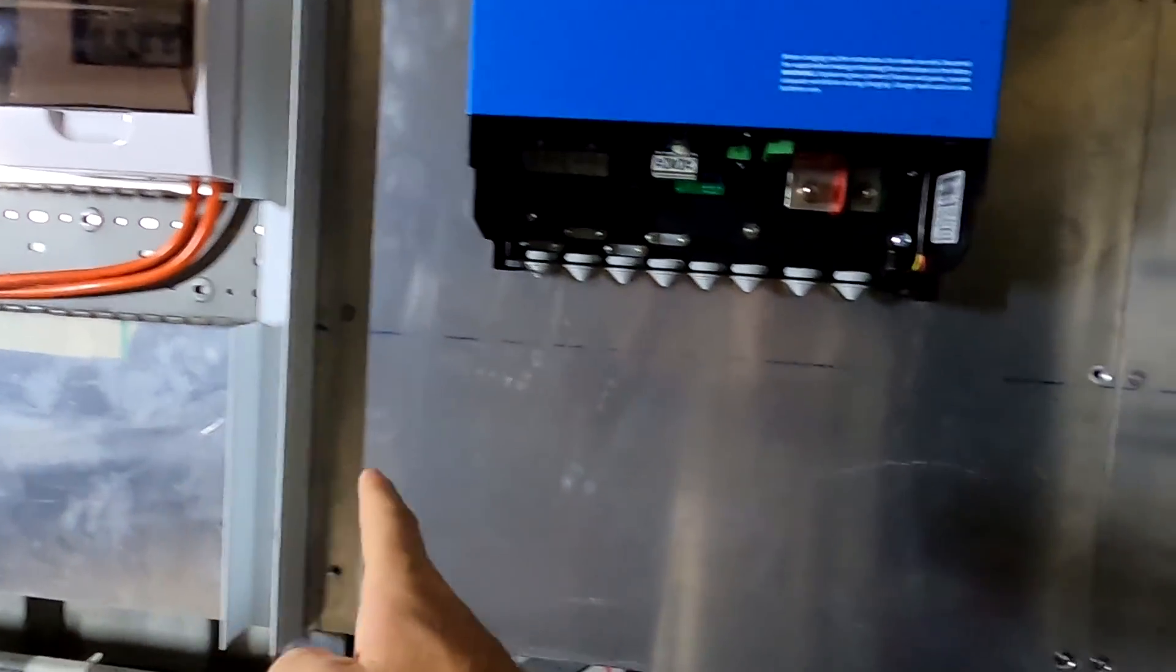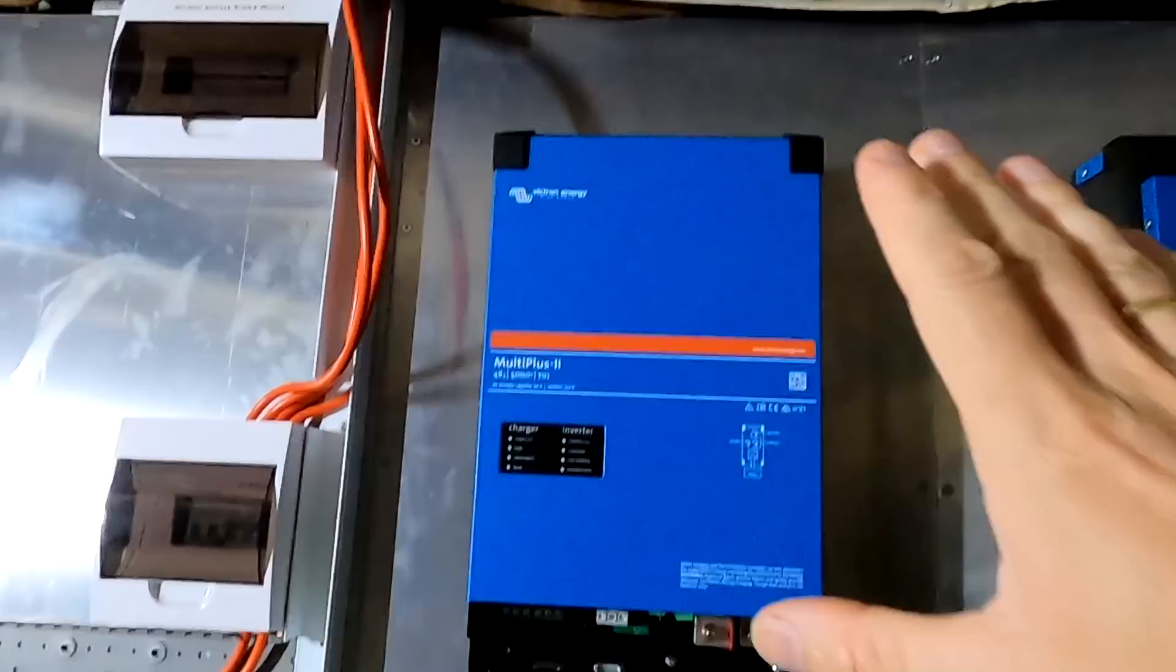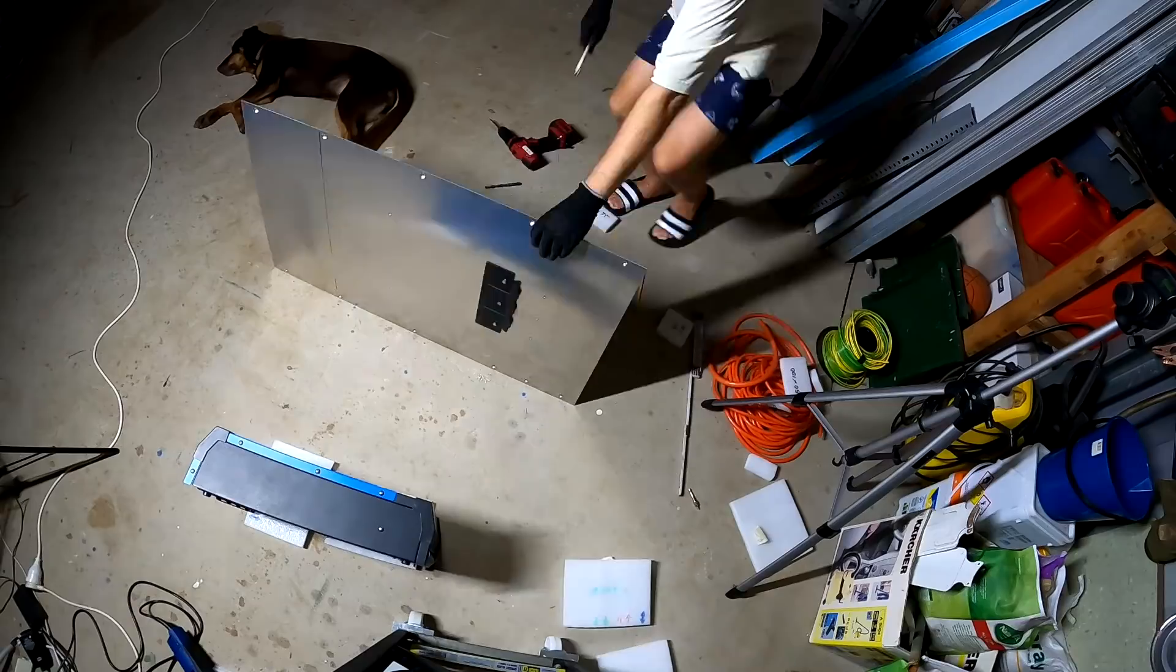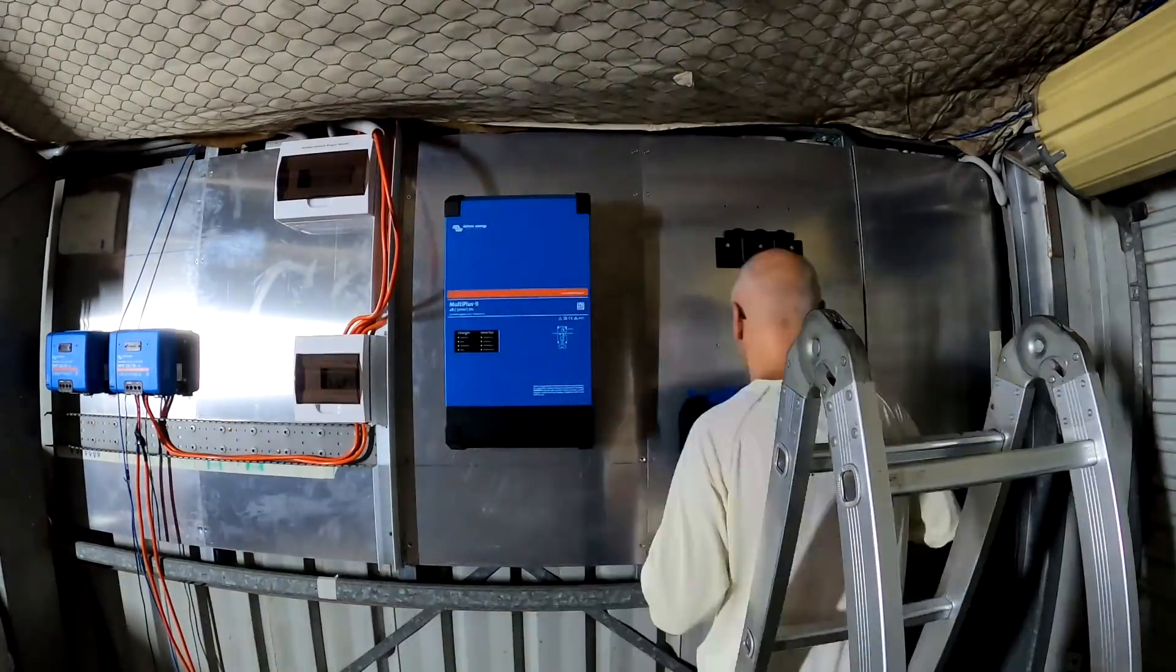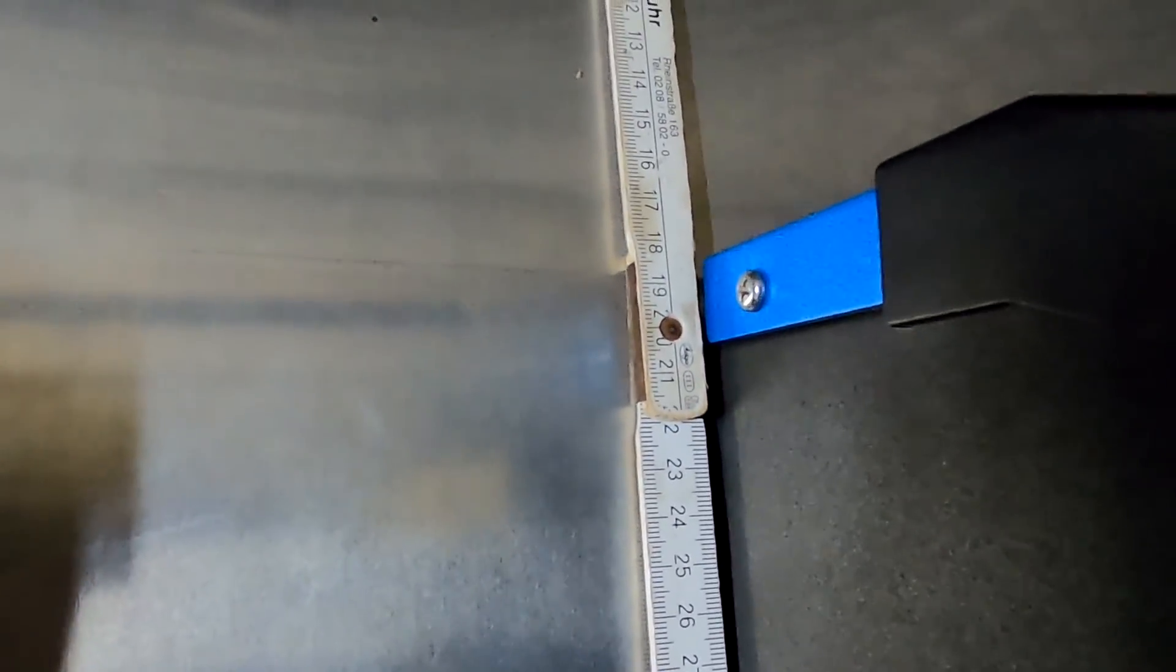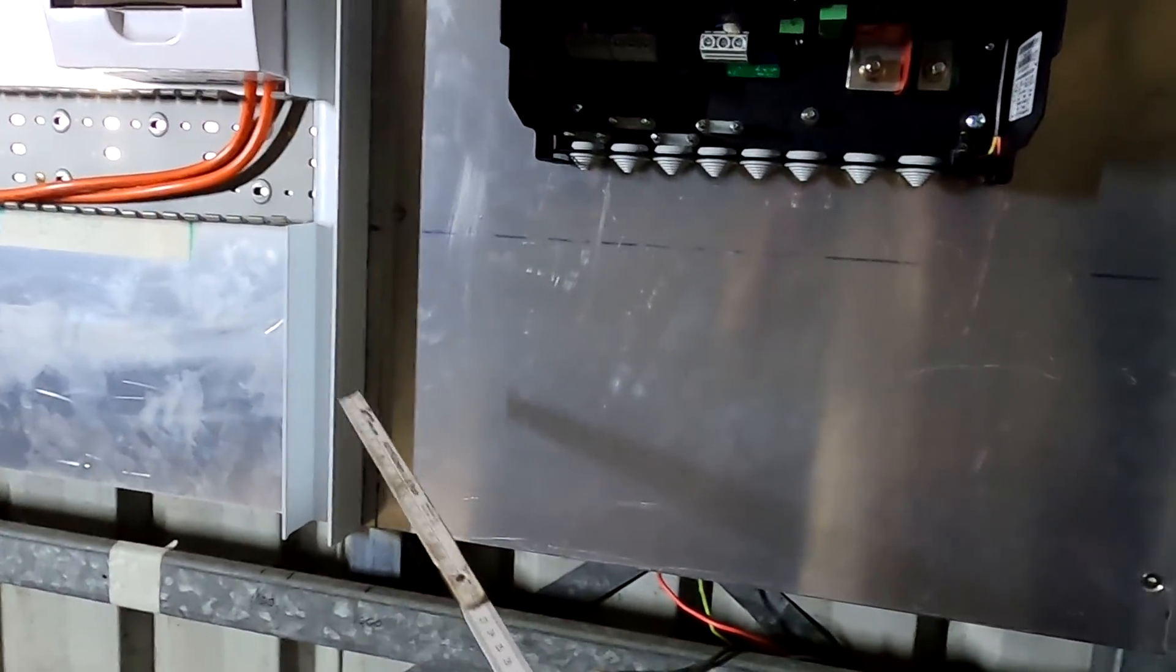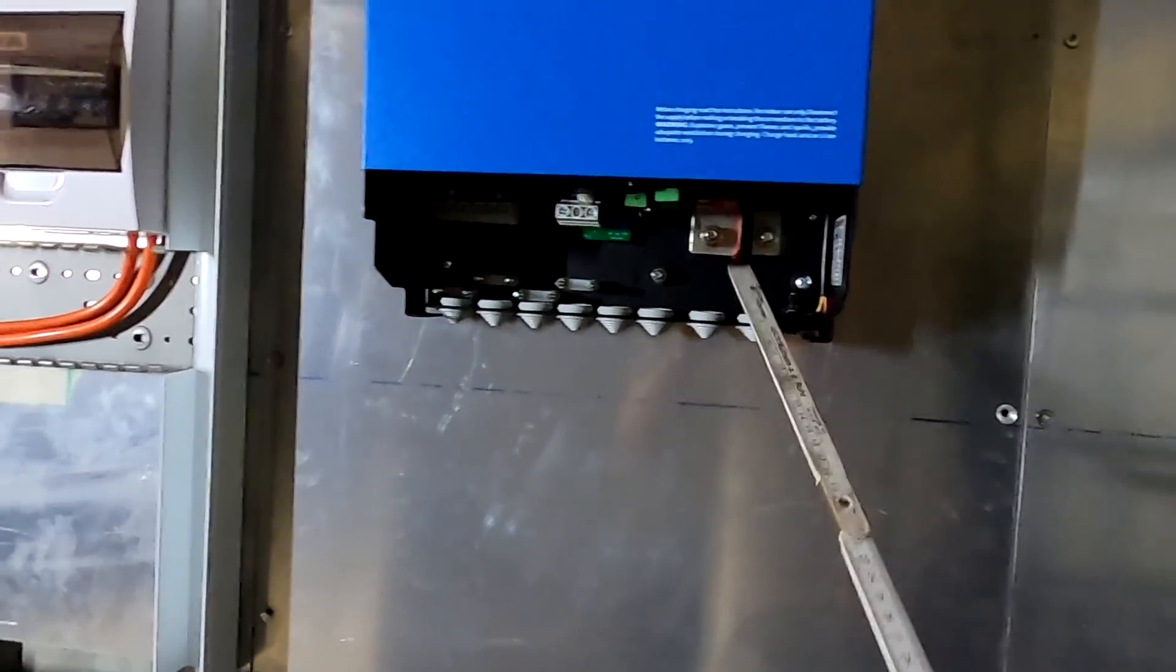Okay, let's get started. We will have DC supply from the bottom to the inverters on both sides and the AC will go out and above the inverters. Maybe you can see it. I have already lowered both of the inverters here by around 100 millimeters. So of course I had to take off both inverters again, had to take off the sheets and drill new holes, measure this all and then put everything back together. So this certainly took me a while. And here now you can see we have around 185 millimeters now space to the top of the aluminum sheet here. And the cable duct is only 50. So that gives us 130 millimeter at the top, good clearance. And we also have enough space down here now to get another main switch in here so we can turn off the inverters at the positive side. Negative needs to stay connected all the time.